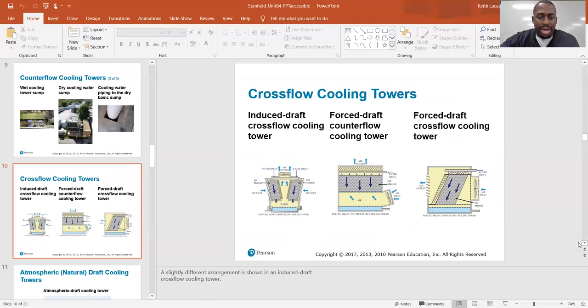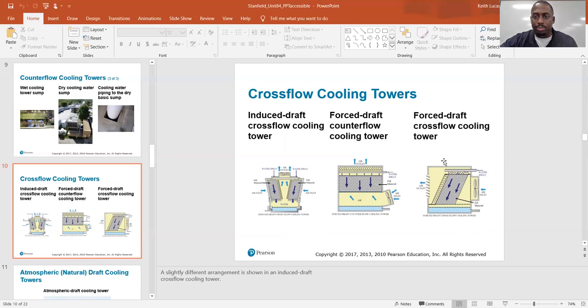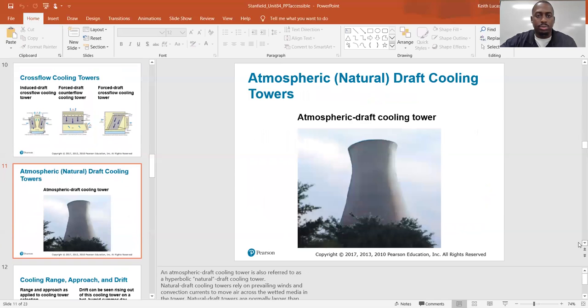Crossflow cooling towers. A slightly different arrangement is shown in an induced draft crossflow cooling tower. The fan is up at the outlet where the air is being released — the air gets pulled by that fan across the wet media and blown out of the top. There's also a forced draft counterflow, where the fan is in the inlet pushing the air out, and the water is going in the opposite direction. And a forced draft crossflow, where the fan is again located in the inlet airstream and blows across the wet media, going across instead of up or down.